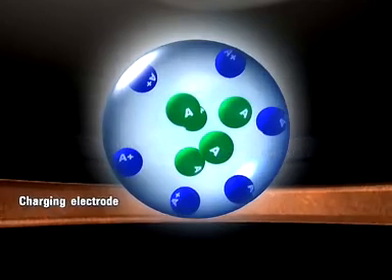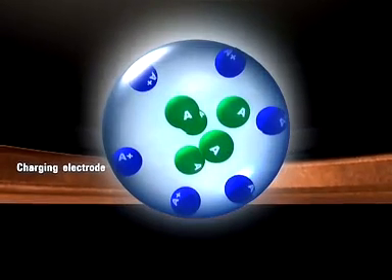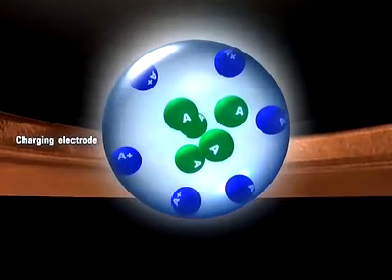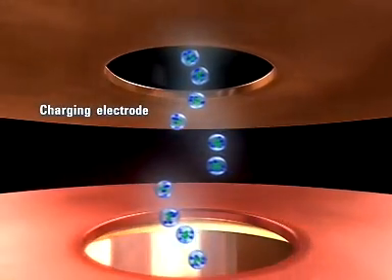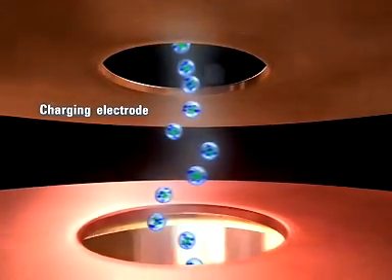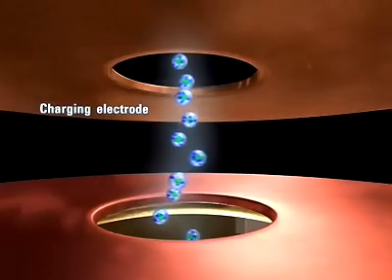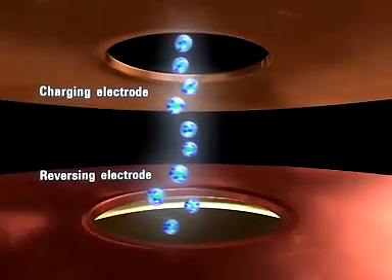Nebulized droplets pass through an electrode that charges the droplets and establishes the preferred ion polarity. Momentum from the nebulizing gas carries the charged droplets through a field established by the charging and reversing electrodes.